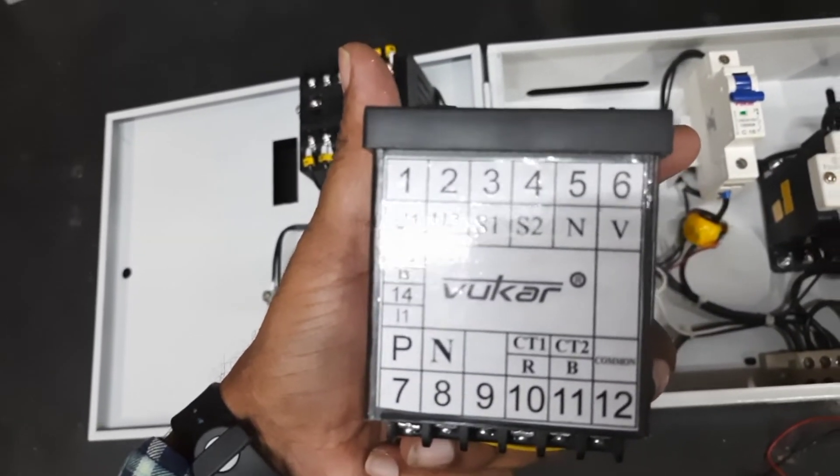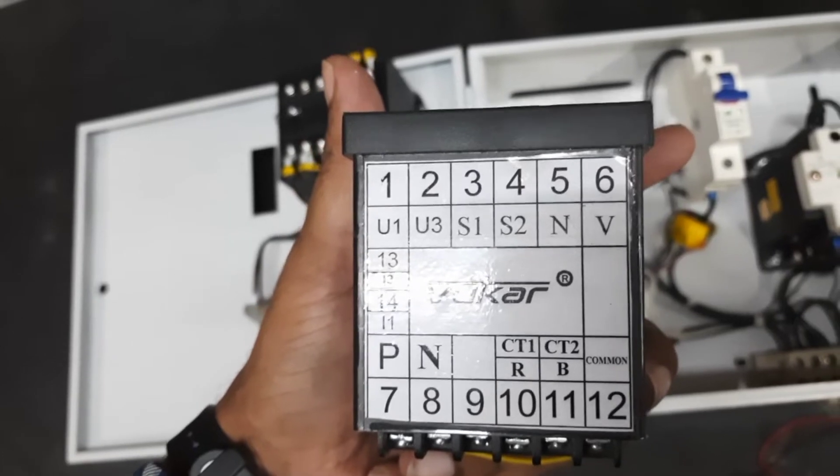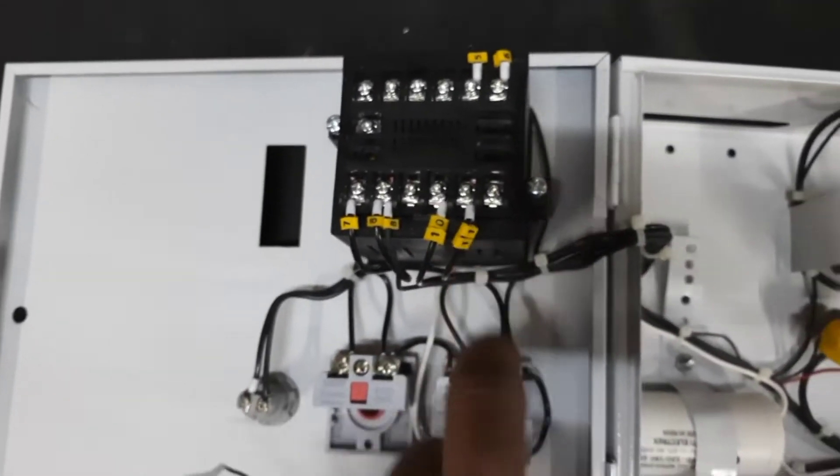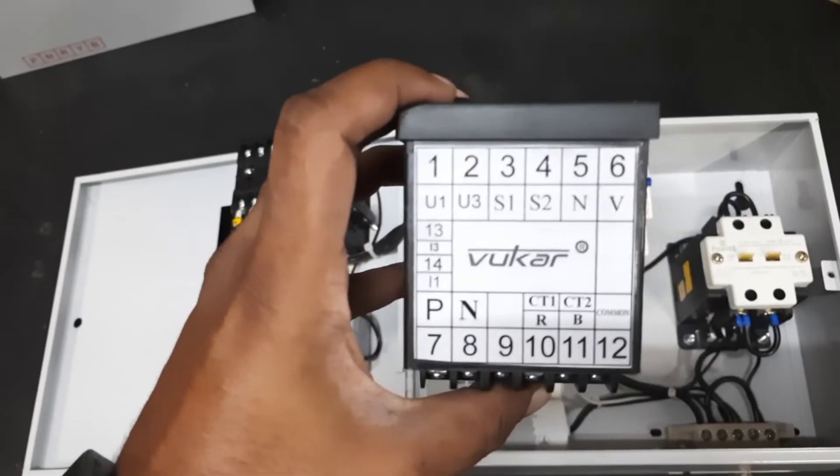Then terminals 10 and 11, that is for the CT terminal. A CT will be provided with the meter, so the CT coil is connected with terminals 10 and 11. Then terminals five and six will be used.